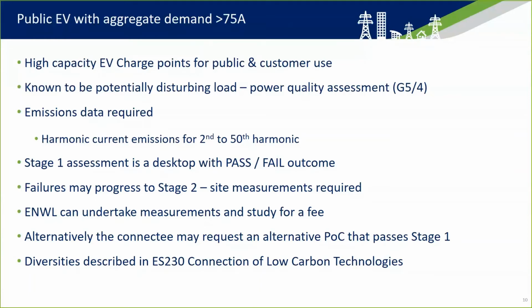The power quality assessment that we follow is a document called Engineering Recommendation G5. It's standard for all the DNOs in the country, and it basically ensures that connecting new devices to the network won't result in power quality issues for that customer or any other customers nearby on the network. It involves basically a two-stage process, and we do need emissions data for the device that's being connected, specifically harmonic current emissions from the 2nd to the 50th harmonic. This will allow the stage 1 assessment to carry on, which gives a pass-fail outcome. It's either within limits or it's out of limits.